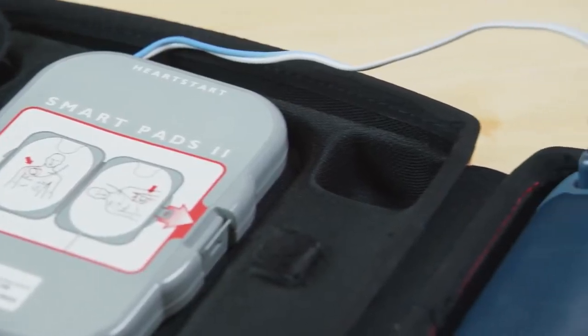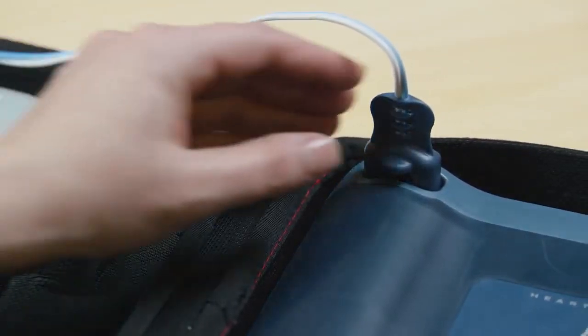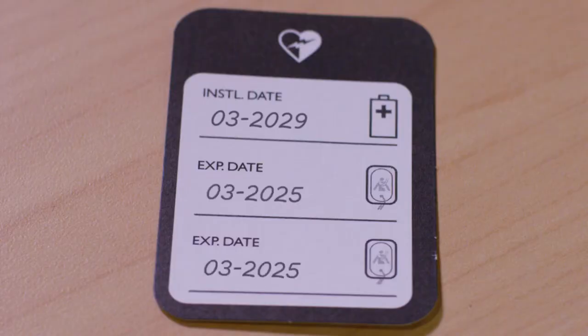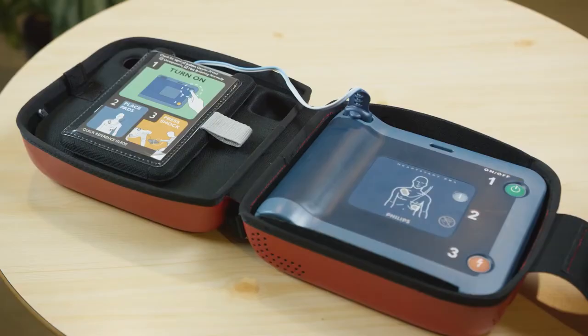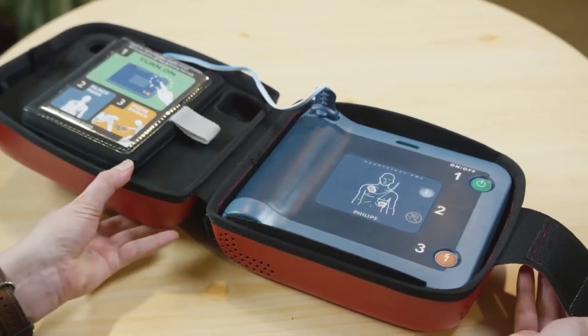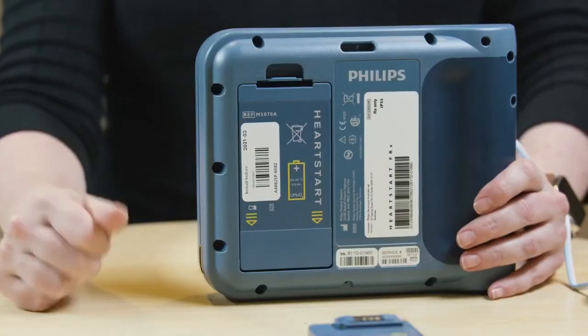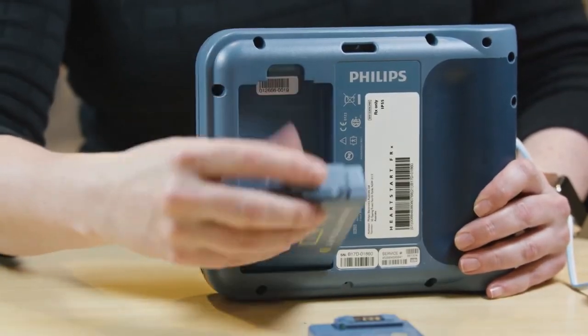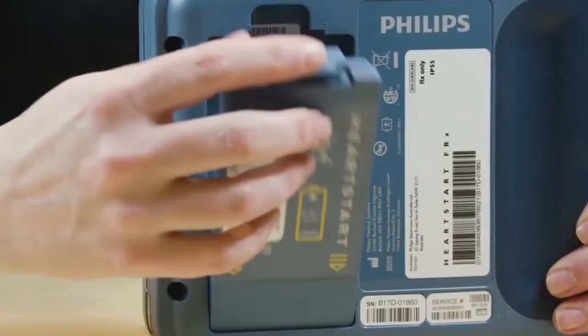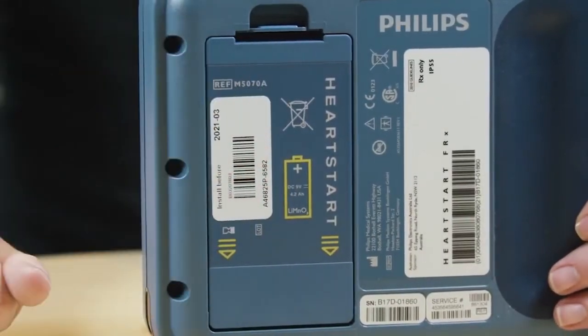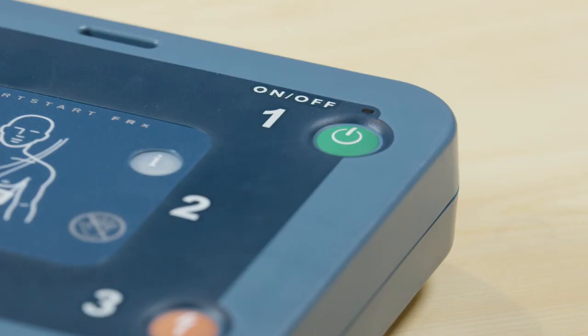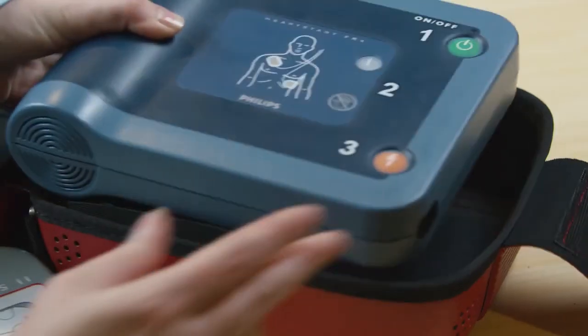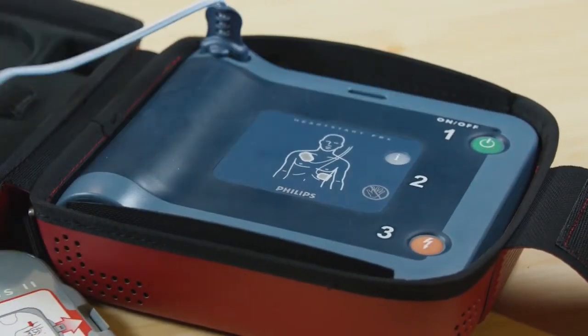Make sure to replace the smart pads after use and record their replacement in the maintenance log. Additionally, do not store the HeartStart FRx with the infant-child key inserted. Unless your local protocol dictates otherwise, remove the battery for 5 seconds and then reinstall it. This will initiate the device's battery self-check and confirm its readiness. Check to see that the green ready light is blinking and return the HeartStart FRx to its normal storage location.